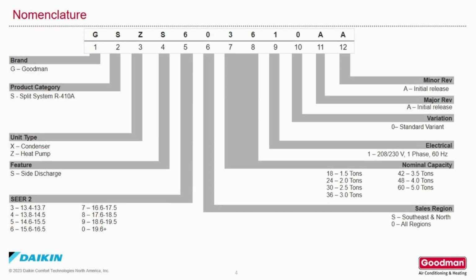Let's familiarize ourselves with the nomenclature. The first position is the brand. The G means Goodman. If it was an Amana, it would be A. If it was Daikin, it would be D, etc. The second position is the product category. S is for split system using R410A refrigerant. The third position is for the unit type. X is for cooling only. Z would be for a heat pump.